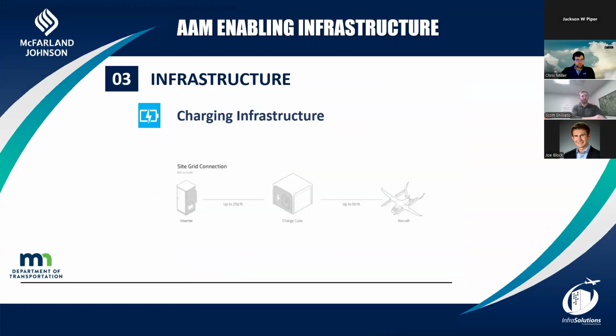So this is your inverter to your charge cube. You have AC power coming in, goes to an inverter, DC power coming out. That inverter needs to be within 250 feet of that charge cube, and then that charge cube 50 feet to your aircraft, because that's your cord length. Really you want a little closer than that because you don't want to be at the end of your cord length. You want to split that difference, but still keep in mind Engineering Brief 105A, which says 10 feet from the end of a wing to a fixed or movable object. So you kind of have your range when you're siting it.